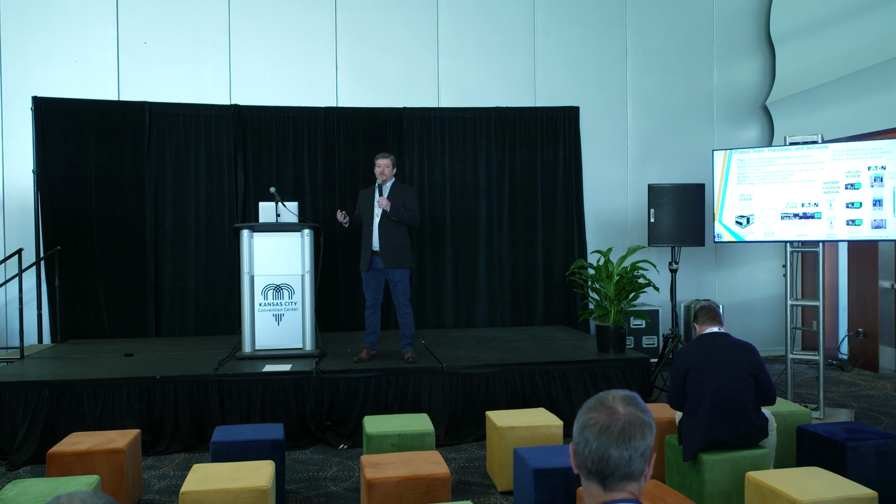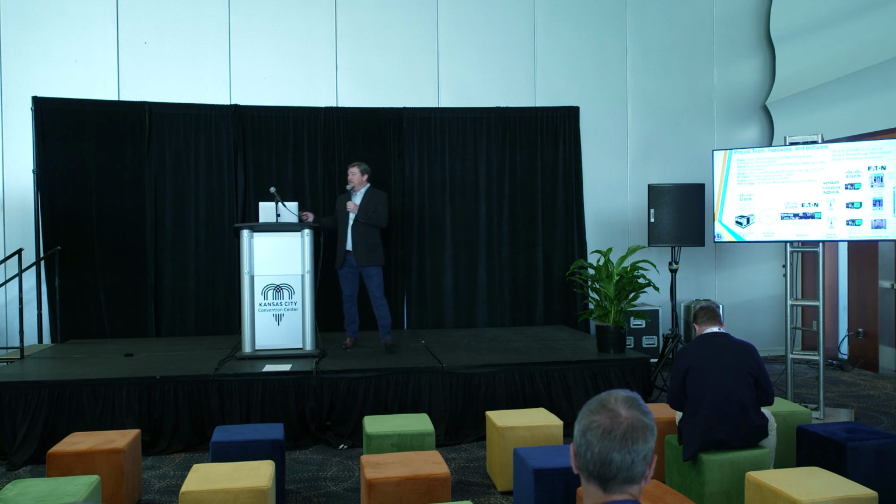optimization. So if you used EMS for improved set points for volt-var, you might have update times on the order of minutes. We did update times on the order of seconds, which translates to significant saving of energy. It could also translate to longer lifetime of your grid assets because they're running in a more optimized state. Stored energy optimization and situational awareness were the other major applications.